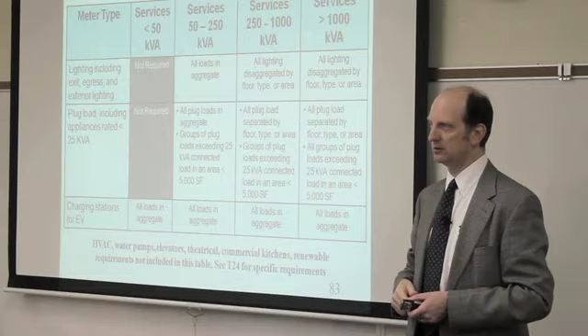You need to know what the plug load is for each of those 3 stories. If you've got groups of plug loads that exceed 25 kVA in a lab area or something like that, you need to know what that load is separately from everything else. This is going to mandate power monitoring equipment that we've never typically had as a requirement before. And the rationale on it is this: you want to save energy, is it actually happening? If you're not saving energy, where is the energy being used?